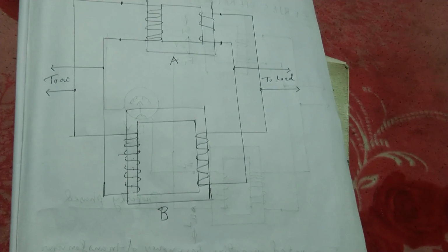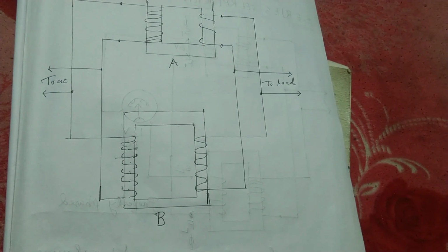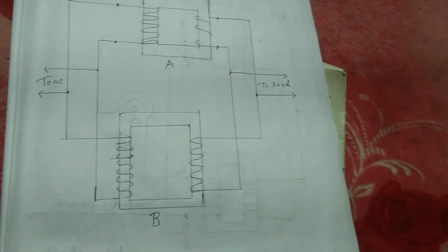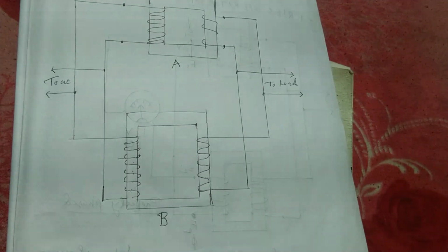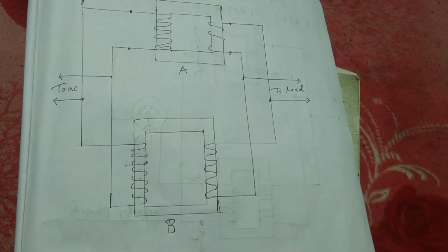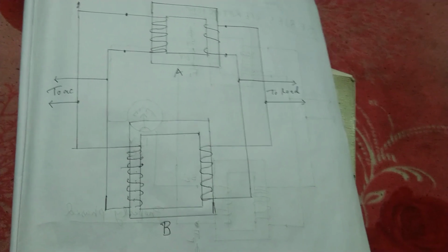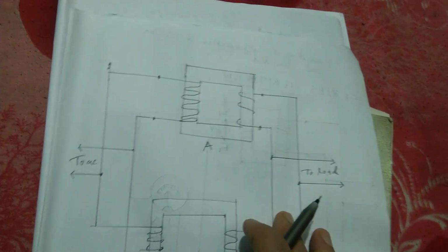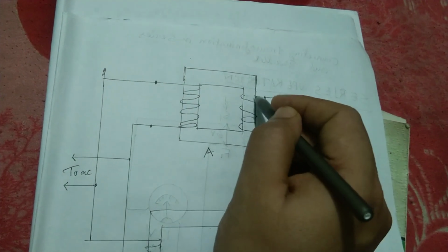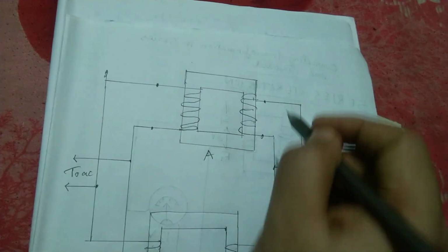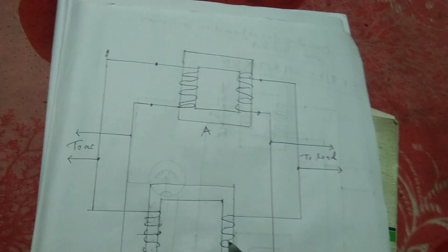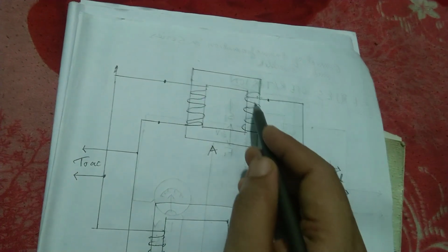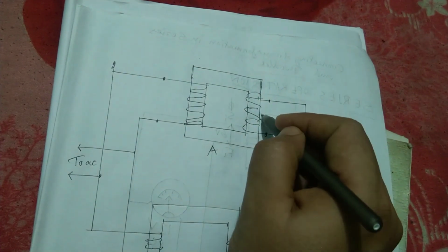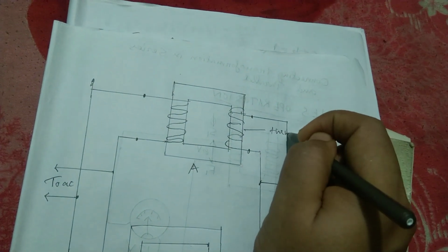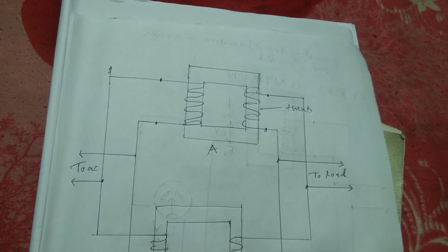If two transformers are to be connected in parallel, the transformers should be alike in every respect. They should have the same number of primary and secondary turns. Maybe the secondary turns are equal or not the same; according to my diagram, let's count it. 1 2 3 4 5. 1 2 3 4 5. Maybe the number of turns is the same. Secondary, same number of turns.